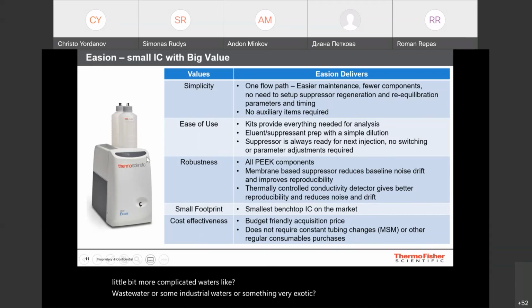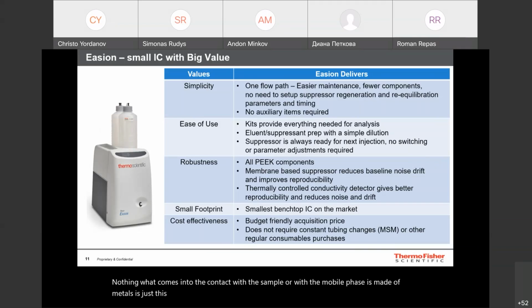Easion, as the name tells us, is an easy analysis of ions. One flow path, easy maintenance, fewer components, no need for special suppressor regeneration parts. Everything is easy, but inert. All components are made of PEEK, polyether ether ketone. Nothing which comes into contact with the sample or with the mobile phase is made of metals. It's just this type of plastic.